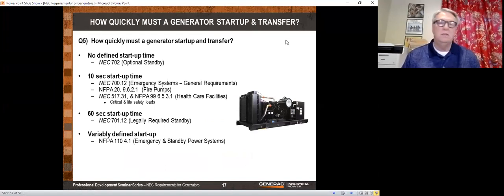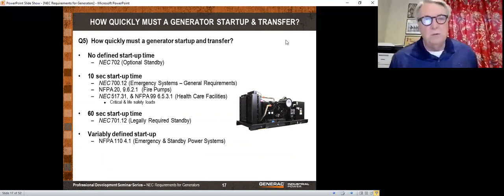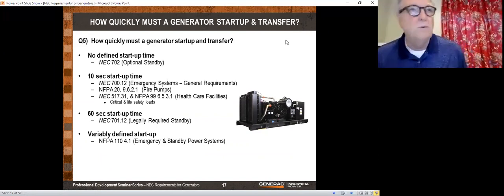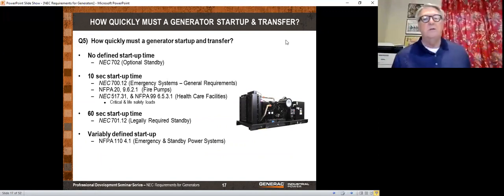Question 5, how quickly does a generator have to start up and transfer? Well, if it's an optional generator, you don't need it there at all, so they don't care. If it takes 6 days for it to start up and transfer, that's fine. You may not be happy with it, but the inspector doesn't care. If it's an emergency generator or a fire pump or critical or life safety loads, which of course would also be an emergency generator, it's got to start up in 10 seconds. And mostly when you hear people say, how quickly does it need to start up, they'll say 10 seconds. But that is actually only for those emergency generators and fire pumps. If it's a legally required generator, you have 60 seconds to start up.